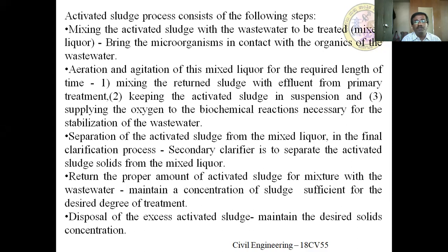Separation of the activated sludge from the mixed liquor happens in the final clarification process, that is the secondary clarifier. The main purpose of introducing the secondary clarifier is to separate the wastewater from the activated sludge and return the separated sludge to the aeration tank. Return the proper amount of activated sludge for mixture with the wastewater, and maintain the concentration of sludge sufficient for the desired degree of treatment.